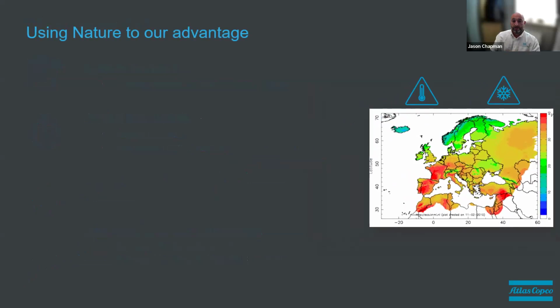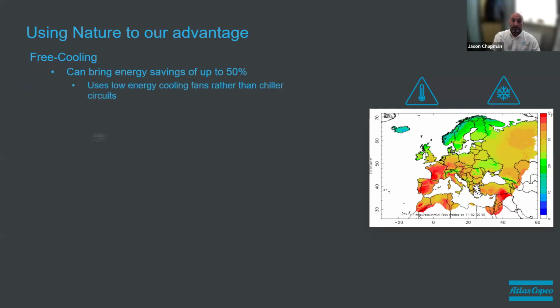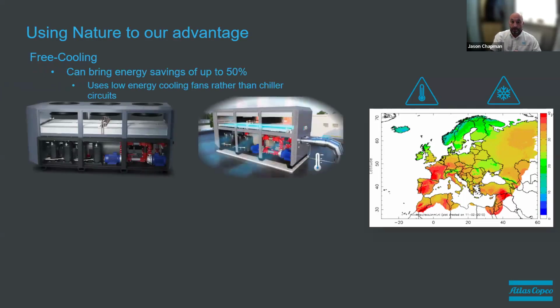How do we use nature to our advantage then? As we said in one of the poll questions, have you thought about free cooling, adiabatic? We're going to discuss free cooling at the moment. So free cooling, what is this? Well, it's the method of using the ambient air temperature around the coolers and the chillers, and using fans rather than a refrigeration circuit. So it uses low energy cooling fans.